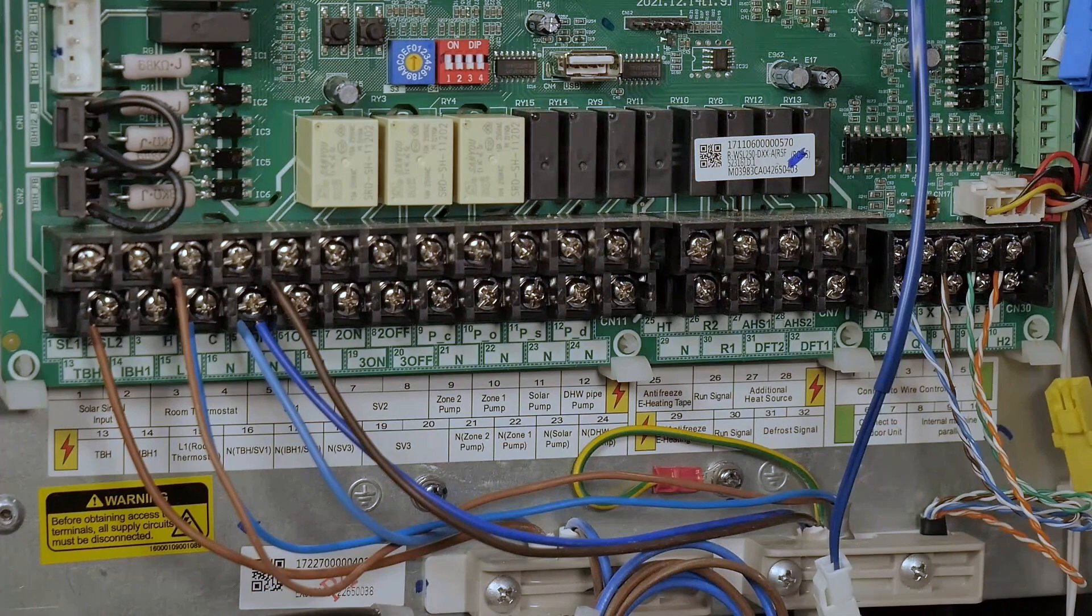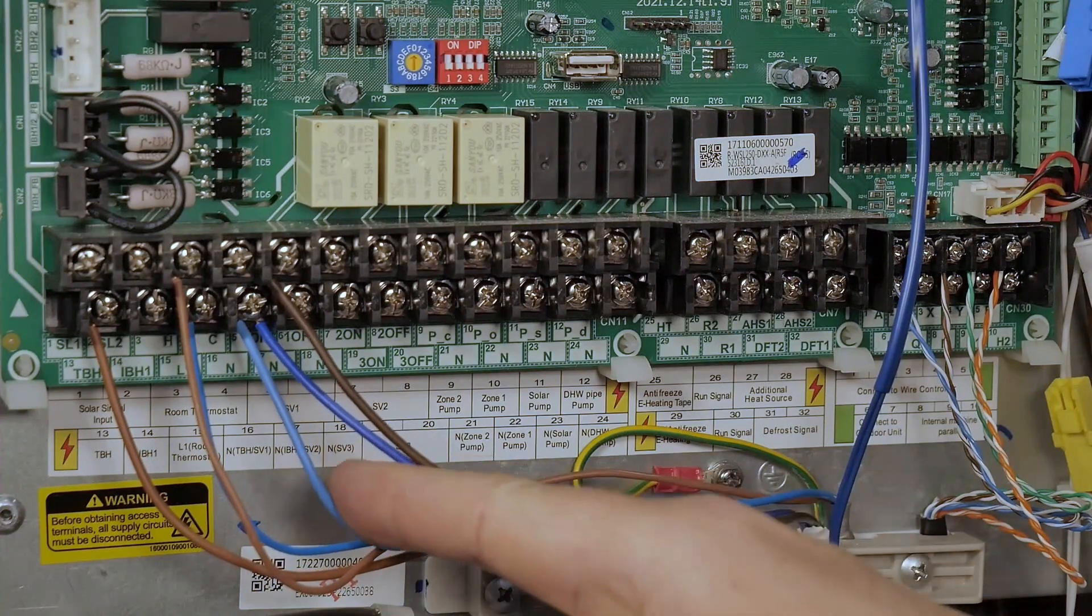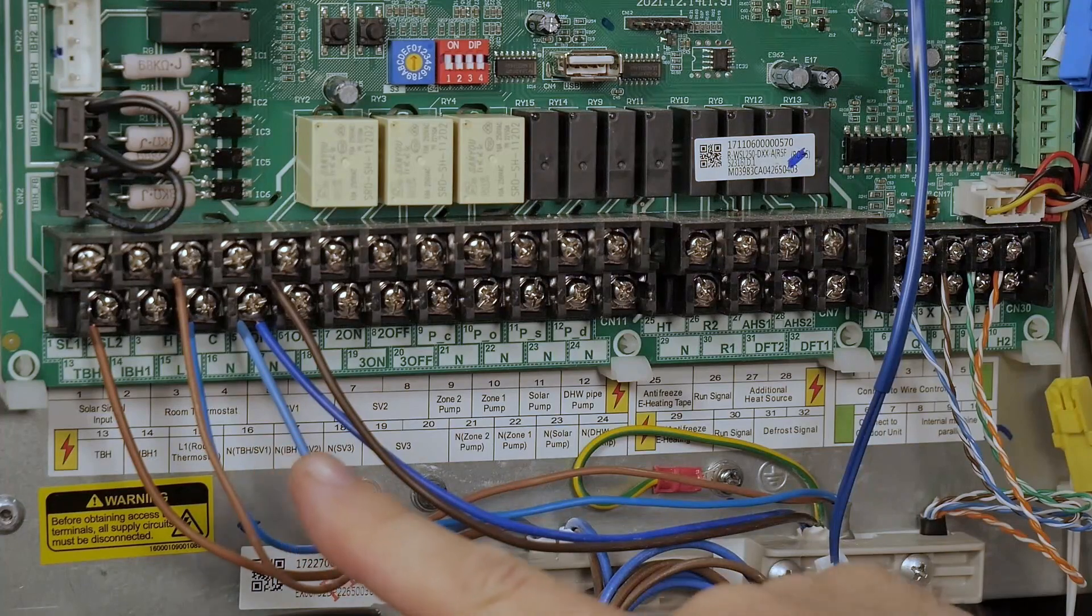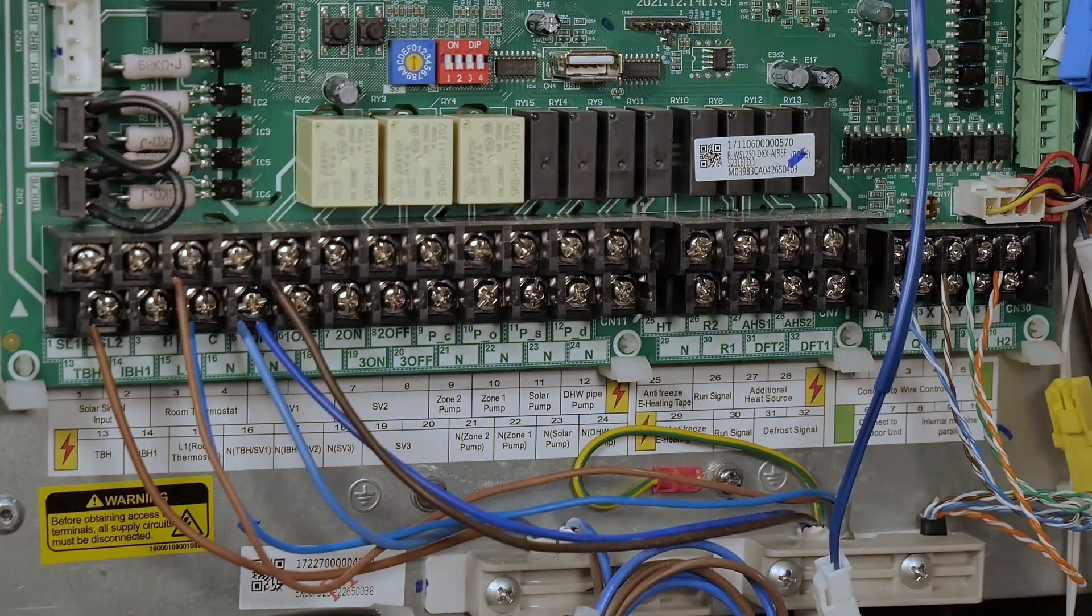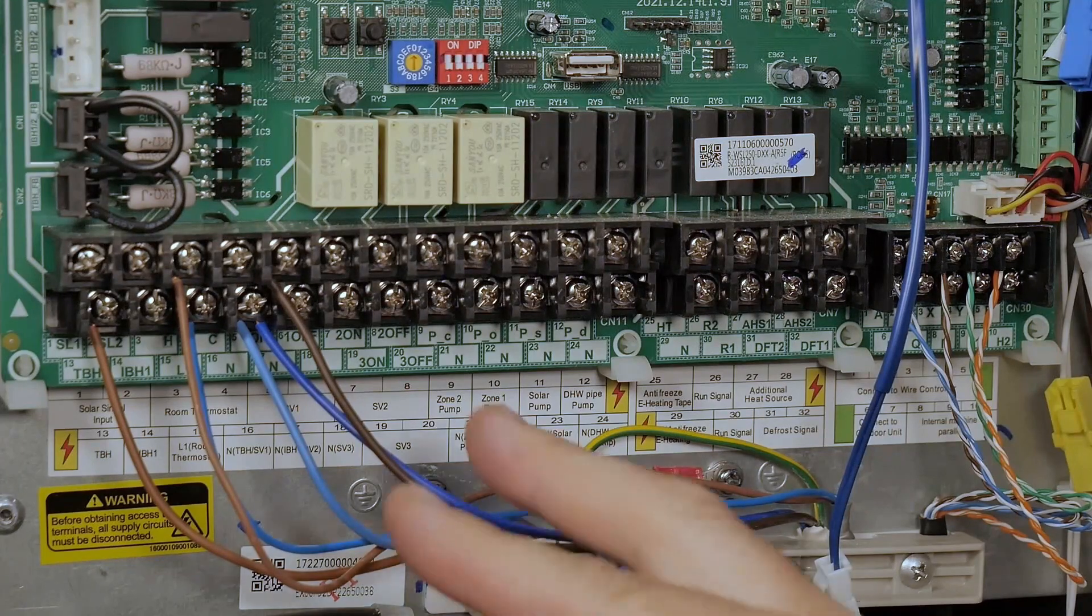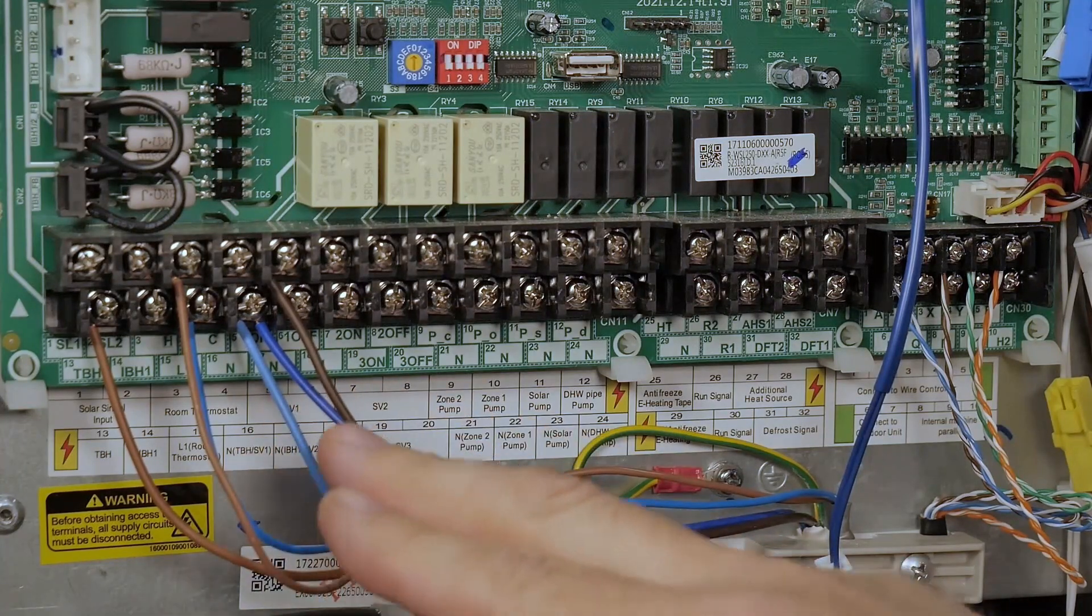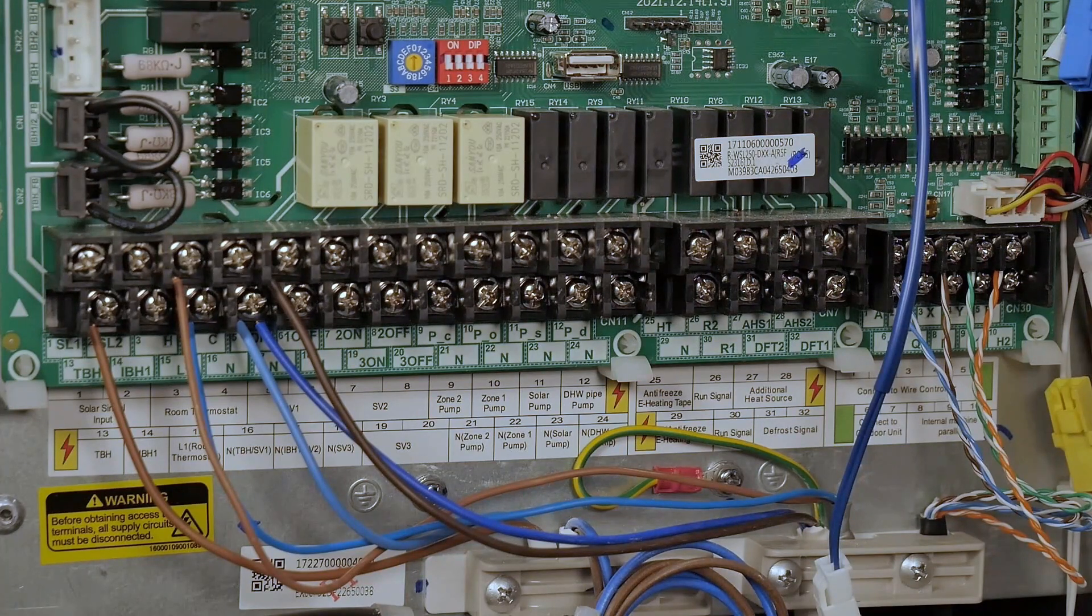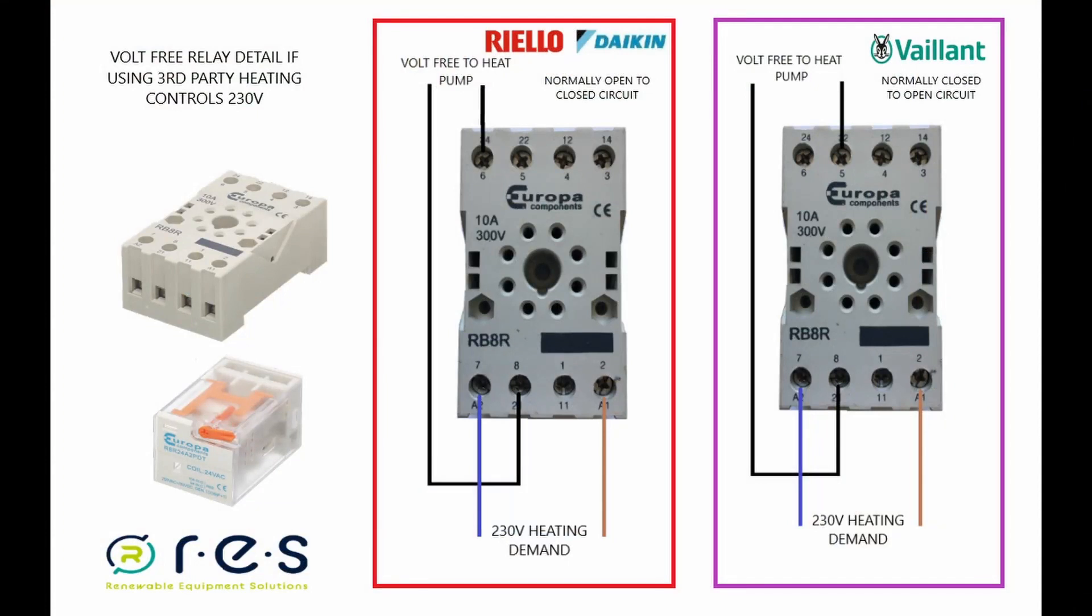If we look to terminals 13 and 16, they're marked for the immersion contactors. With the Riello unit, you will not be able to power an immersion from the contactors here - they are merely a signal to bring in a localized supply that is back near the immersion. So just for reference, you'd need a small contactor that's rated for, say, the immersion would be 20 amp contactor.